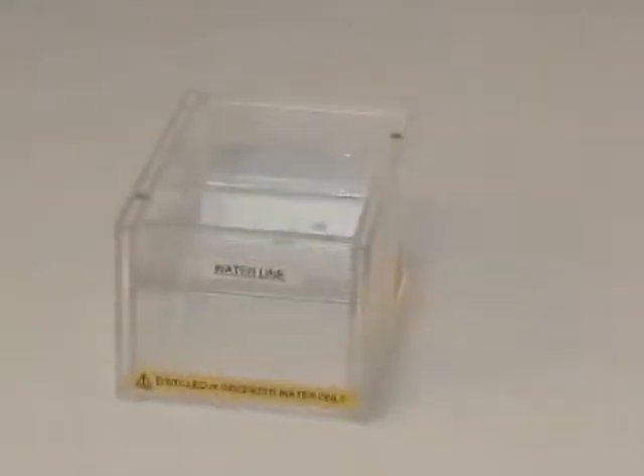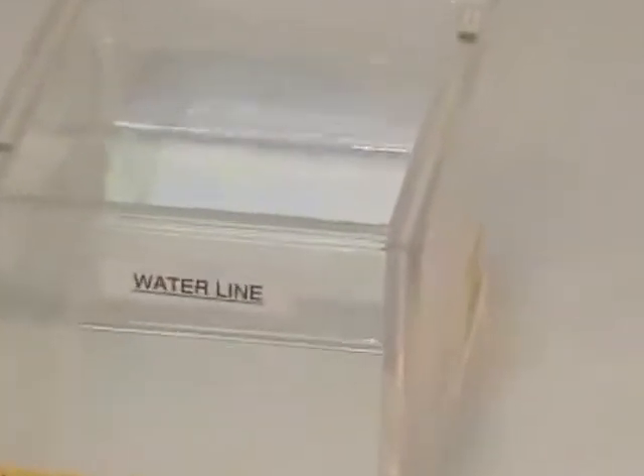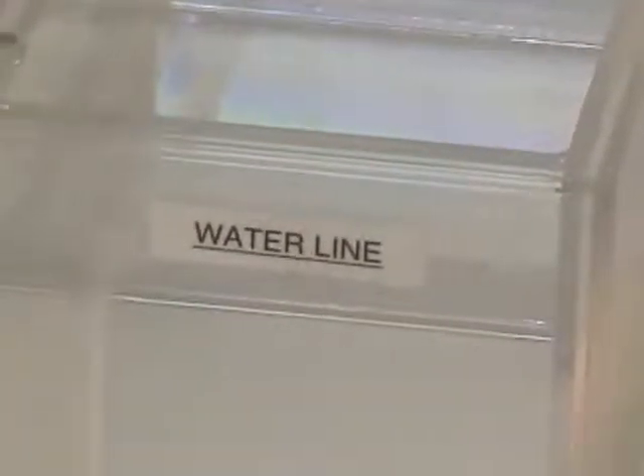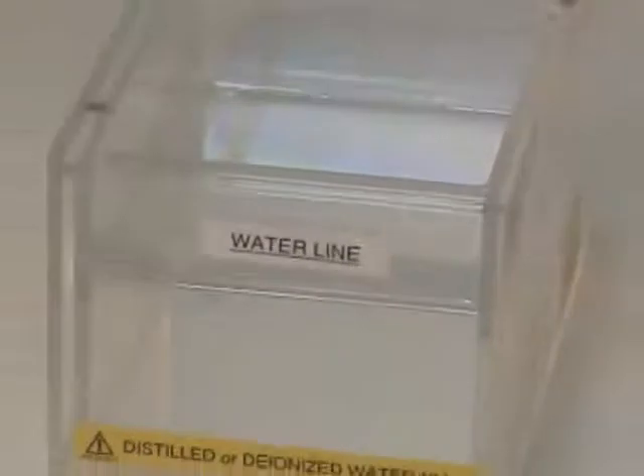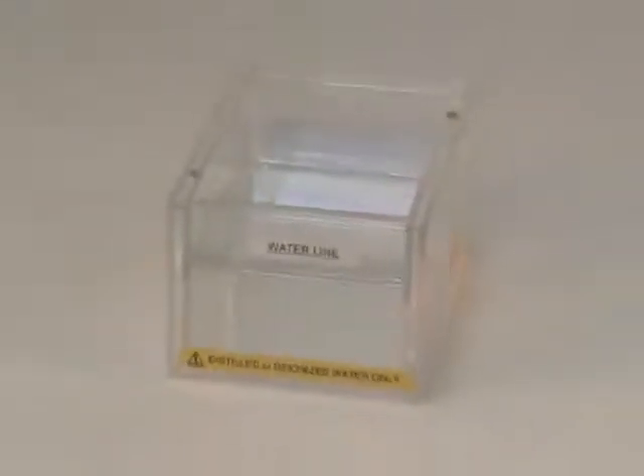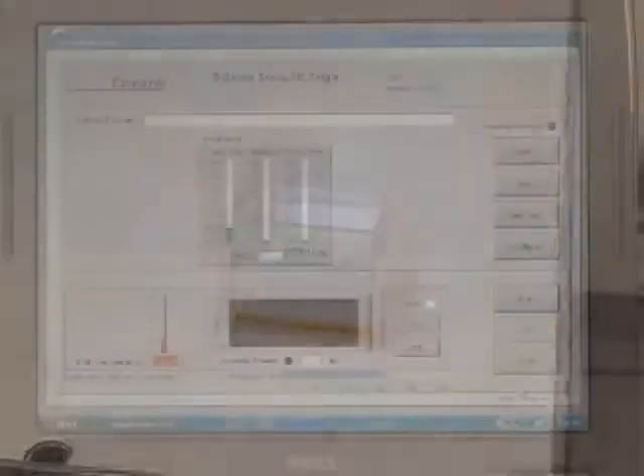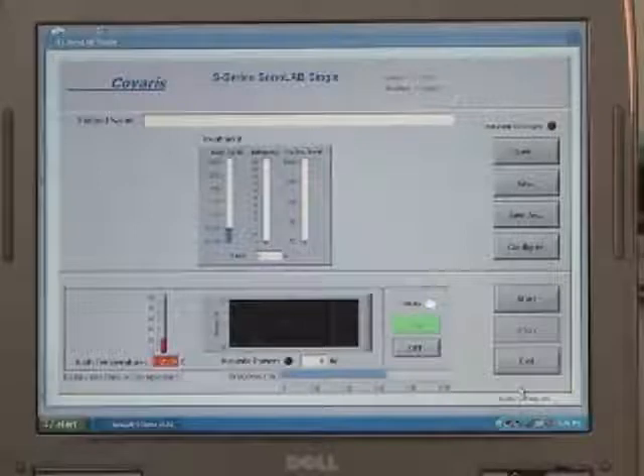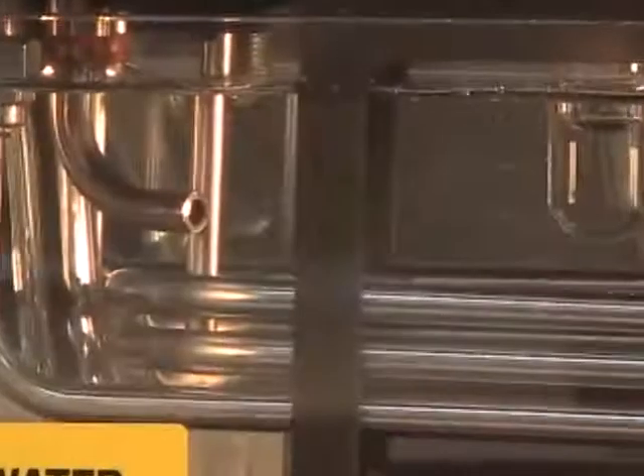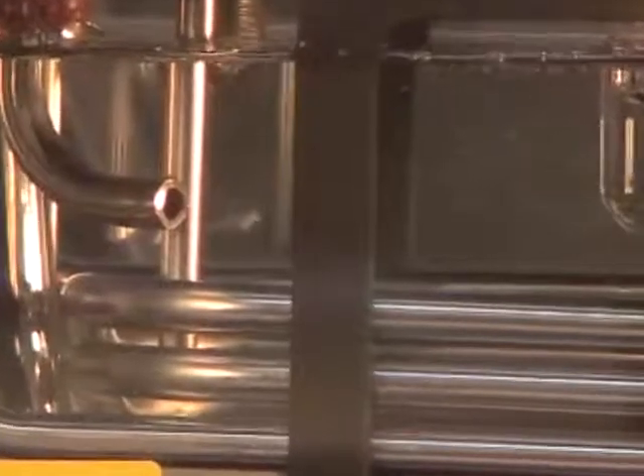Never attempt to run a method without water in the water bath. The quality of the water in the water bath is extremely important for consistent and efficient operation of the S. Only fresh, deionized, or distilled water should be used, and the water tank should be emptied daily. The water in the tank needs to be degassed for 30 minutes prior to running a method. The degassing pump is controlled by the on-off button on the screen. The indicator next to the degas buttons turns green, and a stream of small bubbles can be seen in the water bath. The degassing pump should be left on while the instrument is in use.